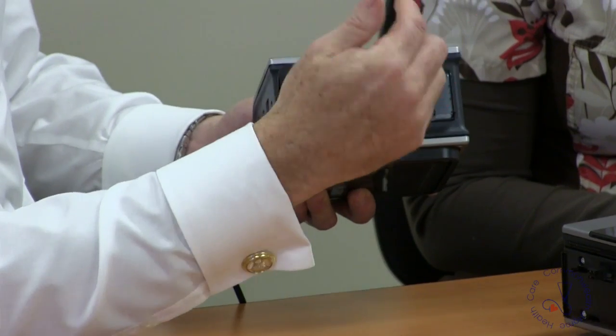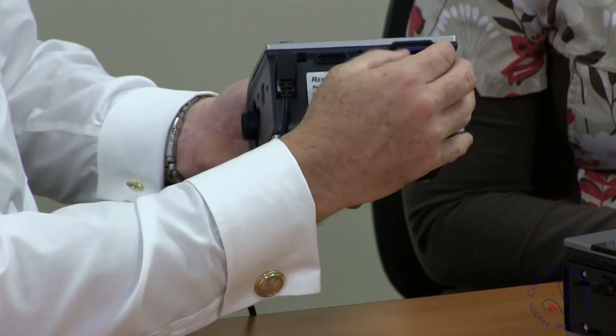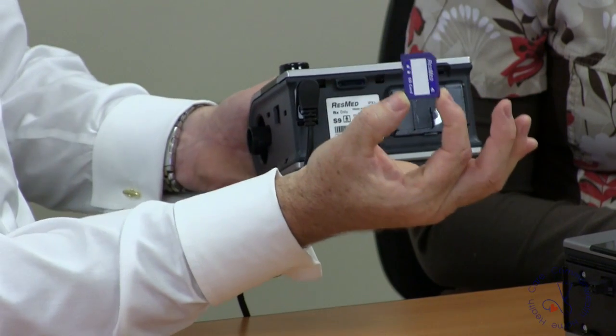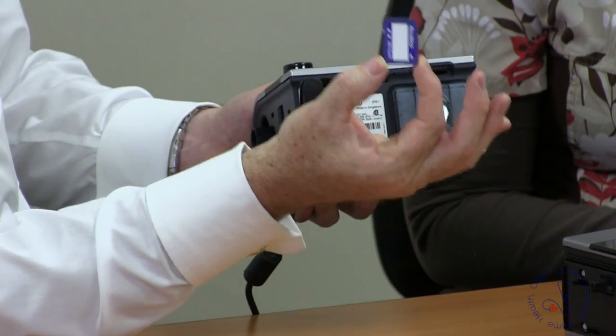The other thing on the back of the machine that sometimes you may have to deal with is your card. It's just like a computer SD card. It just pops out here in the back. You just give it a little push and the card comes out. You would take this to your provider and they would download the compliance data on your machine. It shows your physician how frequently you're using the machine and if you're having problems while you're sleeping at night. This card is going to record that, and so we can help you overcome those problems. It just slides in, a little push, it locks into place. Very, very simple. So that's the CPAP machine in itself.